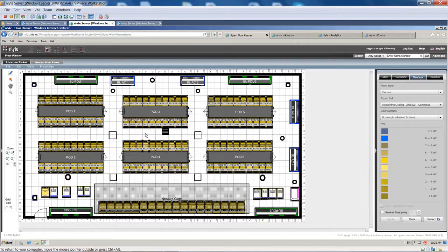We have within the tool a patented methodology that says based on the attributes of assets, things like servers, storage, components coming into the data center and their requirements, and the capacities of the data center, recommend locations of where to put the equipment that can accommodate it. We take many factors into account. Is there space for the equipment? Do I have power? Do I have the network connectivity for that equipment? Am I okay on weight constraints? And this is showing another parameter that's taken into account, which is balancing out of the cooling requirements.